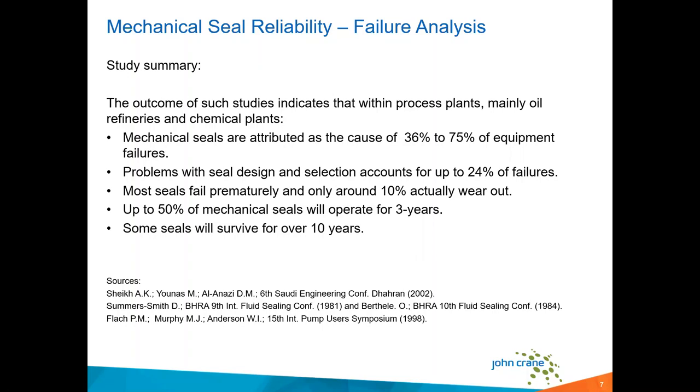Up to 50% of the mechanical seals operated for roughly 3 years. This number, in my opinion, has probably increased over time with more and more adoption of standardized practices like API 610 and 682 for mechanical seals. So I think that number has probably increased some if this study were to be done today. Some seals will still survive in excess of 10 years, and that's still not uncommon, as technology and material improvements in sealing technology become more and more prevalent in the industry.